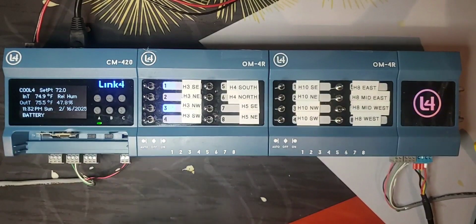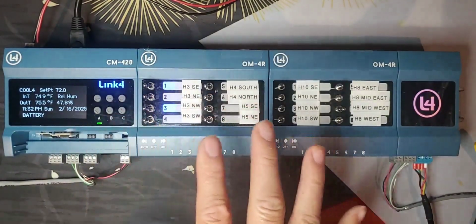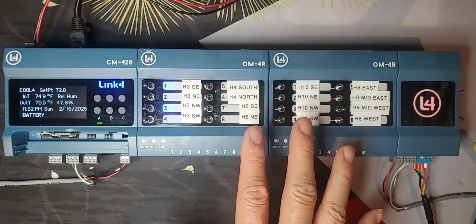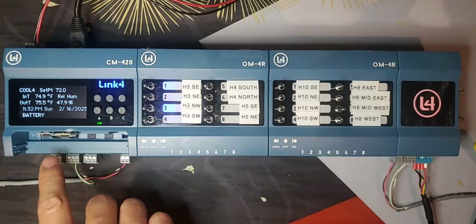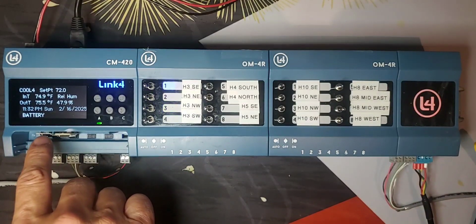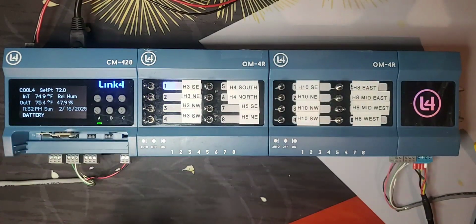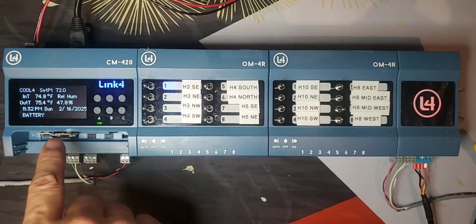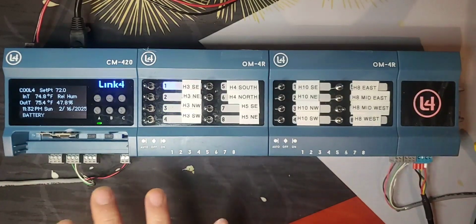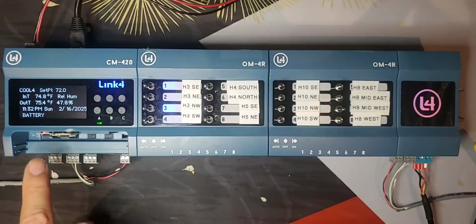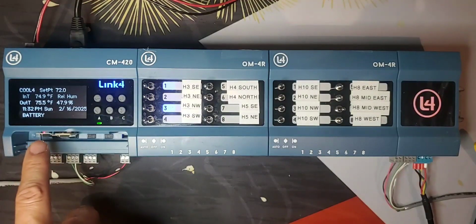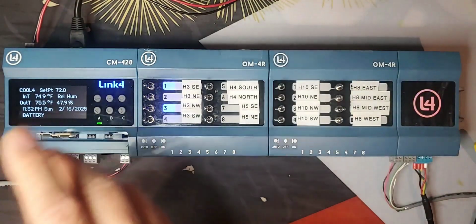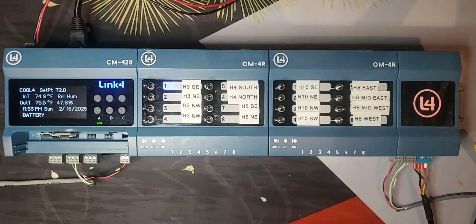Okay, so that's a quick overview on how to troubleshoot the communication on this unit. The other place you look is the light here. Maybe it's hard to see in the video, but you see it flash a little bit. Now, some of the older modules, you might see the lights reversed, but we don't have too many of those anymore. Most of them should be like this, where every time data is transmitted, it turns on briefly.